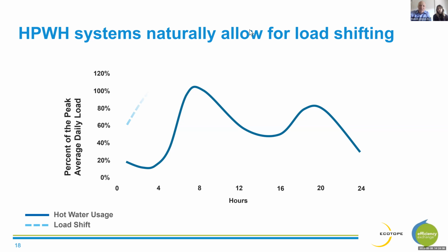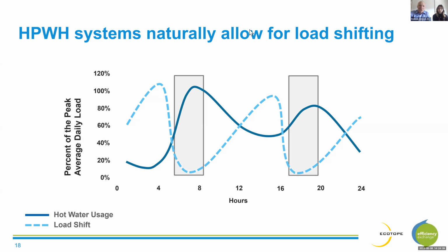So we would like to instead operate electric heat pump systems so that they run overnight when perhaps the wind is blowing and not a lot of people are using electricity. They run during the middle of the day when the sun is out and solar power is being generated, and they're not running during those times when everybody else wants electricity, during that peak cooling time and peak morning warm-up time. So at Bayview, we tried to demonstrate how much time during that morning peak we could shut the system off, and shut it off in the evening, and still deliver consistent hot water.